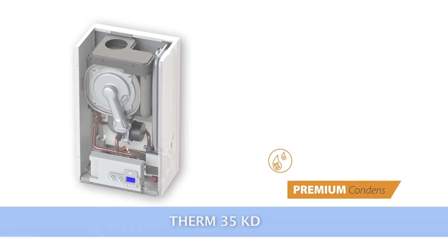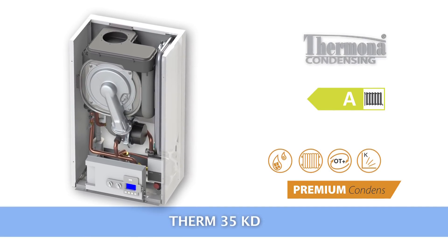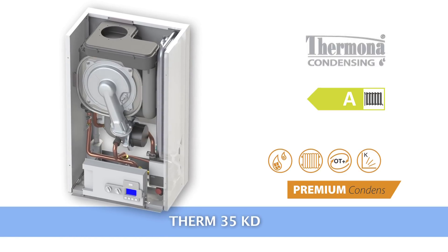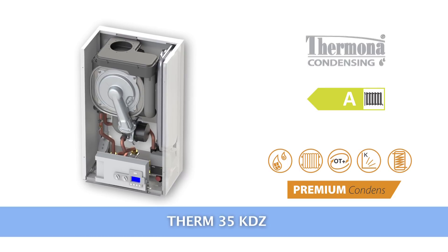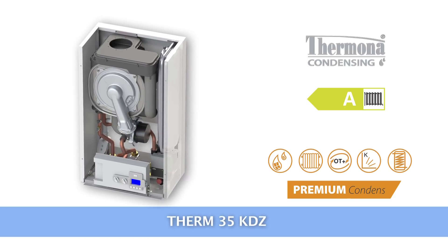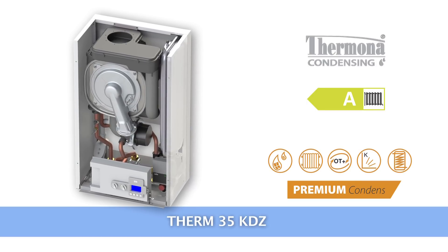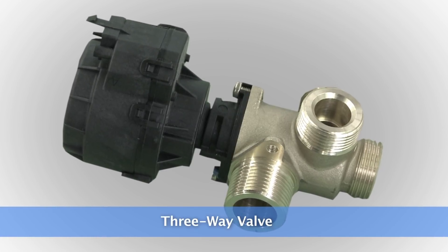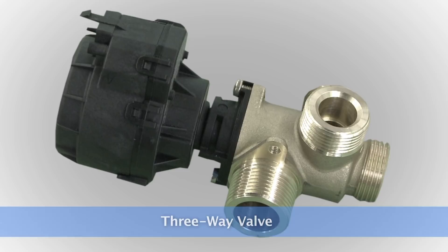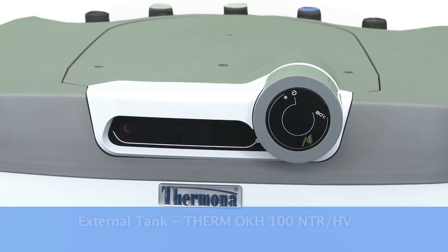Three types of the boiler are offered. The Therm 35 KD is used just for the heating system, not for heating water. The Therm 35 KDZ is used for the heating system and for heating water in an external tank. The boiler has an inbuilt 3-way valve under the casing, which helps to heat an external hot water tank.